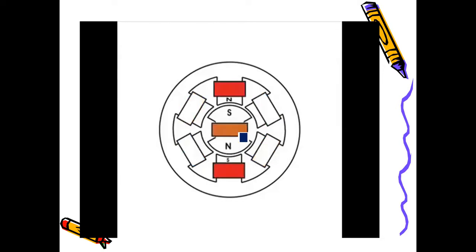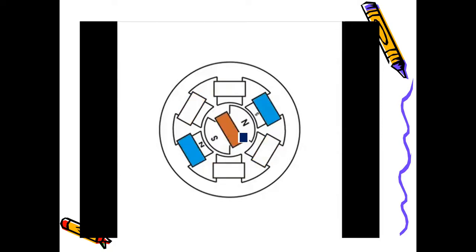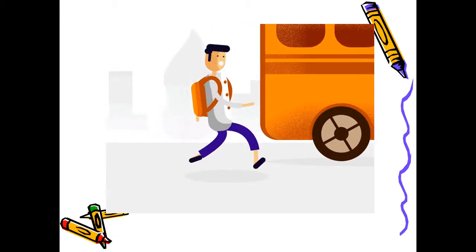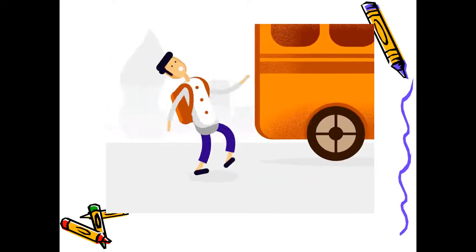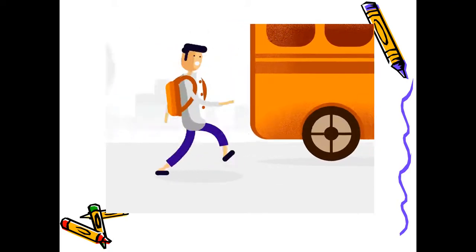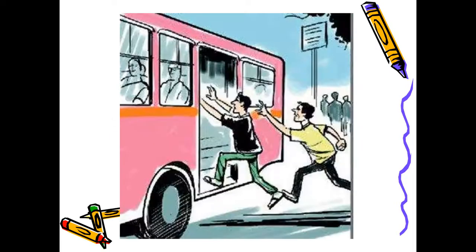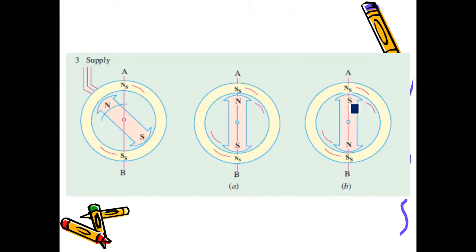The revolving flux is moving but the rotor is stationary. To catch up to the synchronous speed, consider a moving bus — if you want to get into that bus, you have to run behind it and match its speed. Similarly, for the synchronous motor, some prime mover has to rotate the rotor close to synchronous speed, and then it will lock in and rotate continuously.